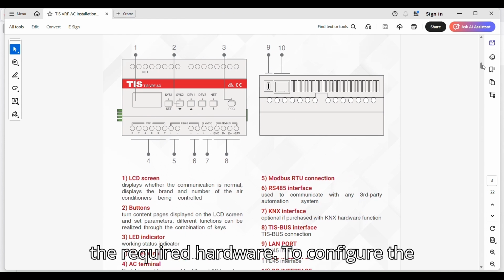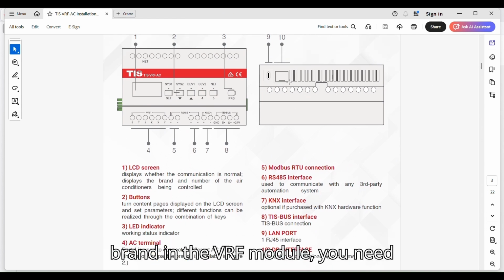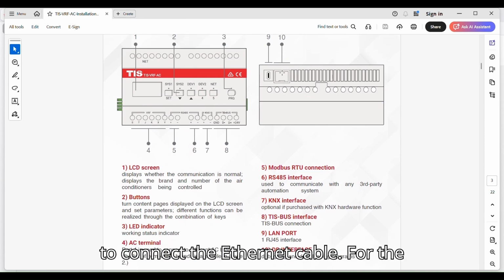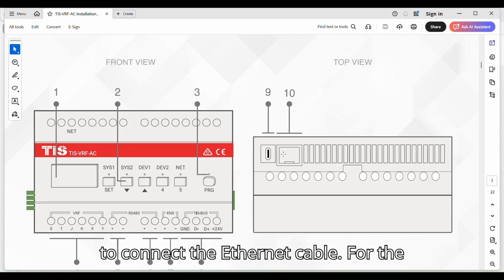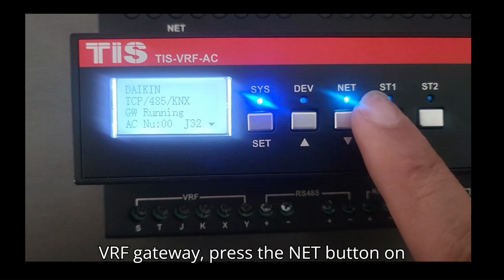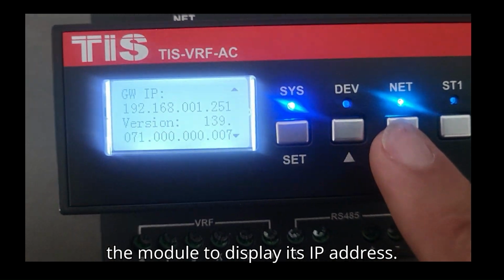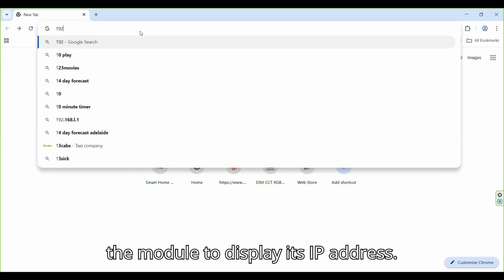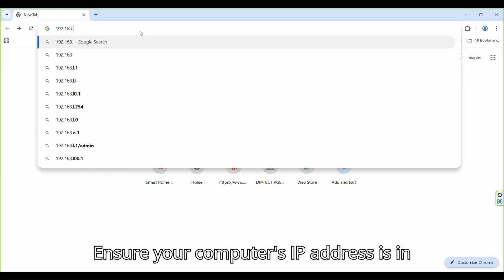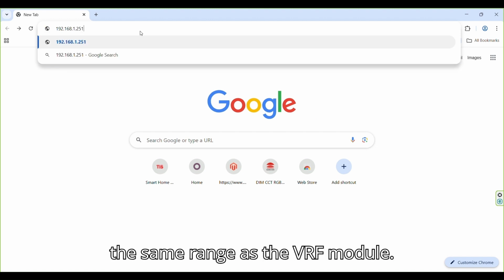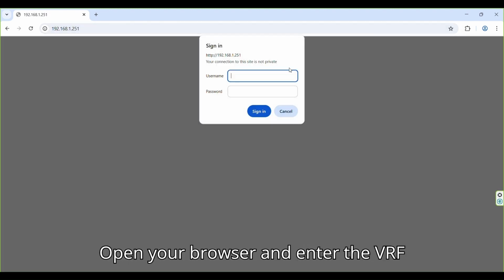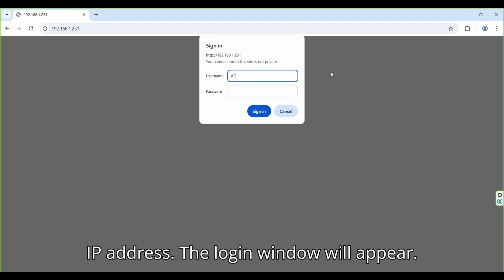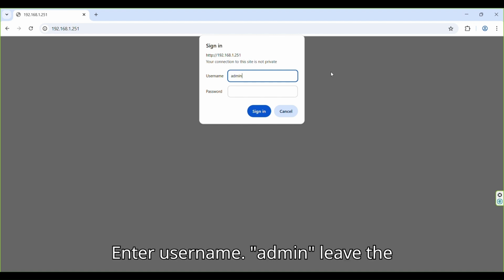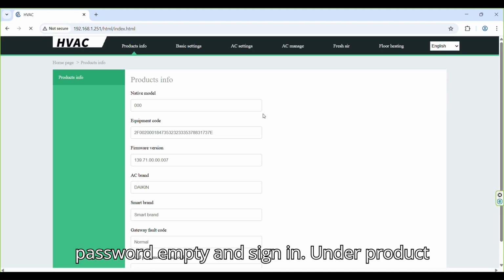To configure the brand in the VRF module, you need to connect the Ethernet cable to the VRF gateway. Press the Net button on the module to display its IP address. Ensure your computer's IP address is in the same range as the VRF module. Open your browser and enter the VRF IP address. The login window will appear. Enter username, admin, leave the password empty, and sign in.